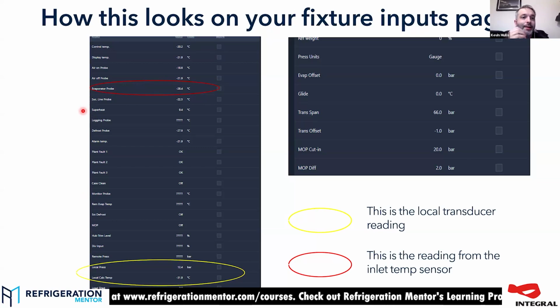So if that transducer goes funny and stops reading, for whatever reason, it will default to using the evaporator probe, which is circled in red. And that is the temperature probe you have on your coil inlet. But as you can see, there is a considerable difference between what they're reading. And if you're controlling to 6K superheat, then you've suddenly lost 3K pretty much by switching to the probe. And inlet probes are not a particularly accurate way of measuring evaporating temperature, because they are highly dependent on where you fix the probe, how well you fix the probe, and how thick your pipe is.